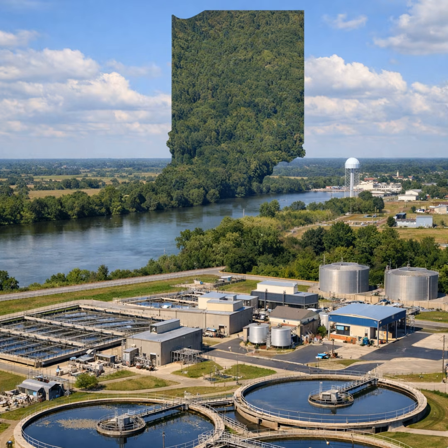Modified aeration. Modified aeration is characterized by a high food to microorganism ratio, low sludge age, a short aeration tank detention time, and high mixed liquor suspended solids. High rate aeration should be followed by other BOD and suspended solids removal processes to provide secondary treatment. So modified aeration is what would be characterized in that type of mode of activated sludge.